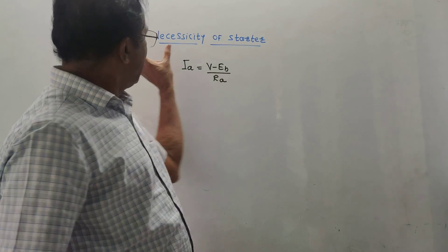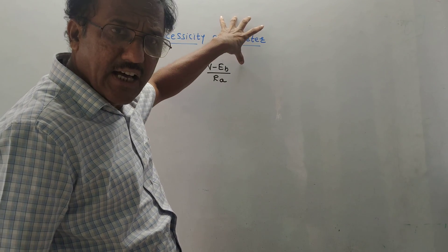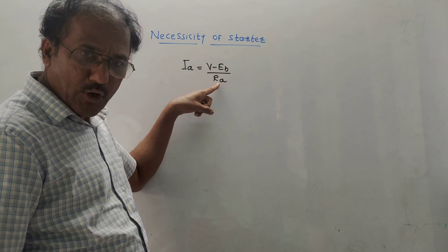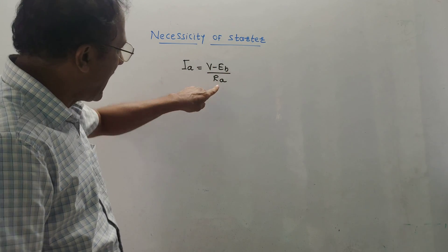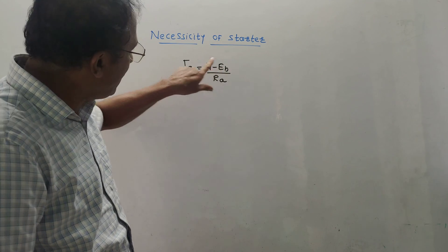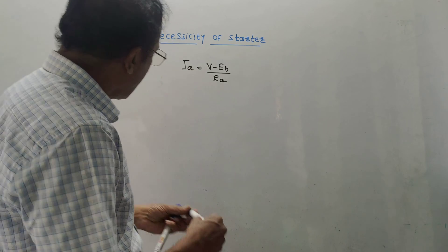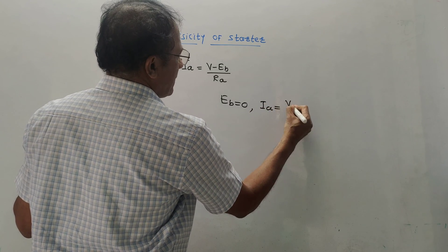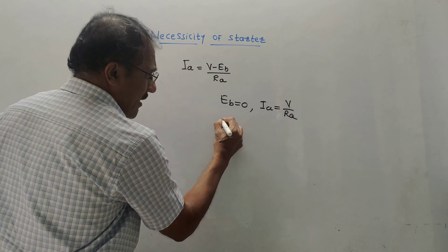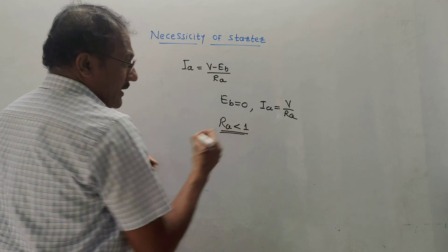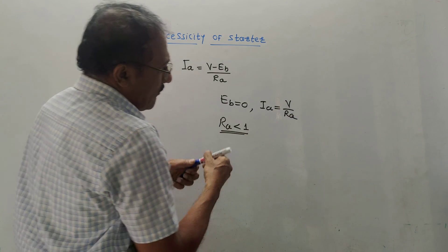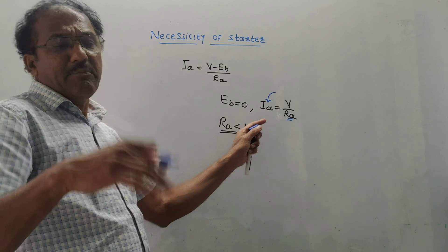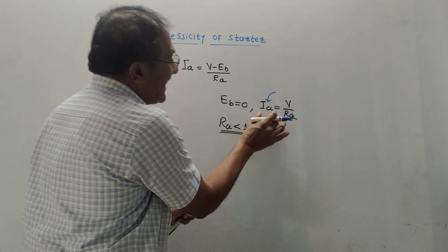The next important part is the necessity of starters for a DC motor. IA = (V − EB) / RA. Initially when you start the DC motor, value of EB is 0. So armature current becomes IA = V / RA. Since value of armature resistance RA is very small — less than 1 ohm — V divided by a small value produces a very large armature current IA, which may damage the armature winding.